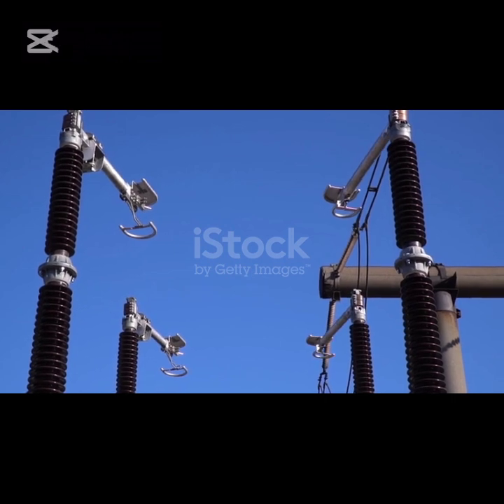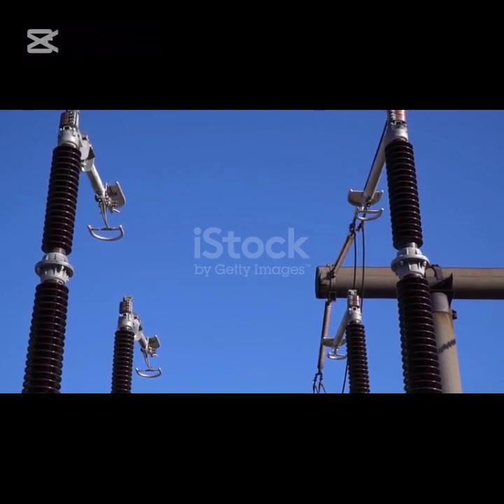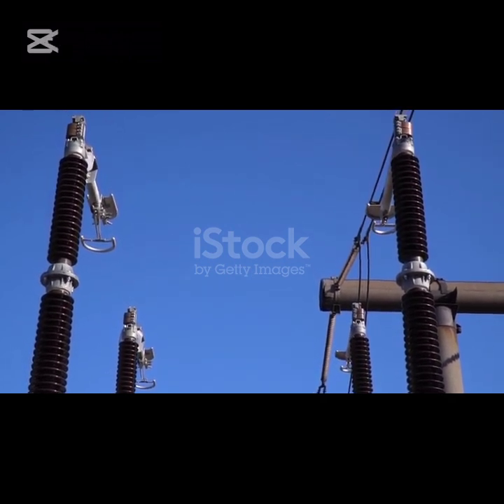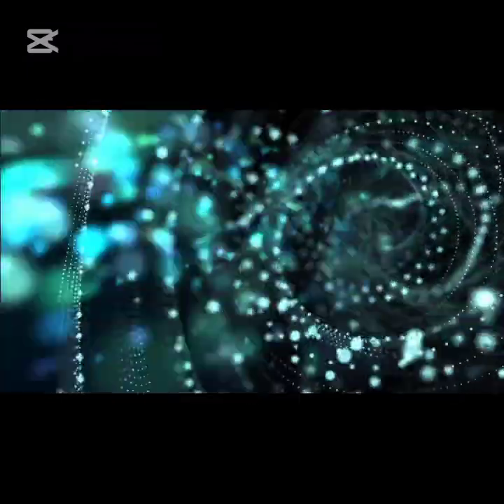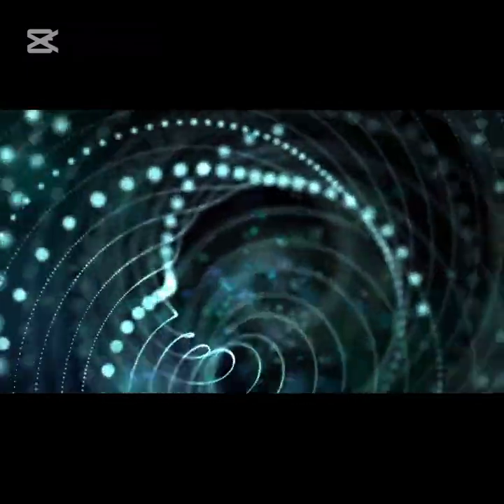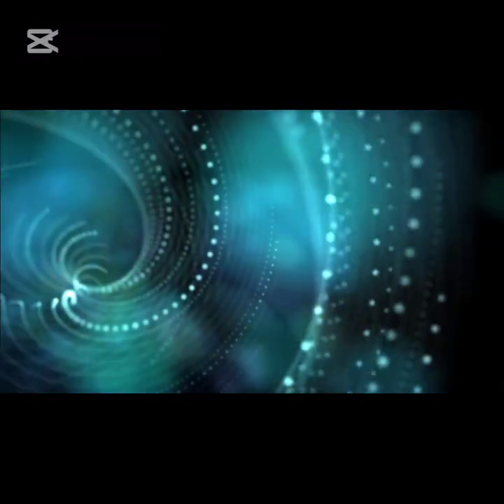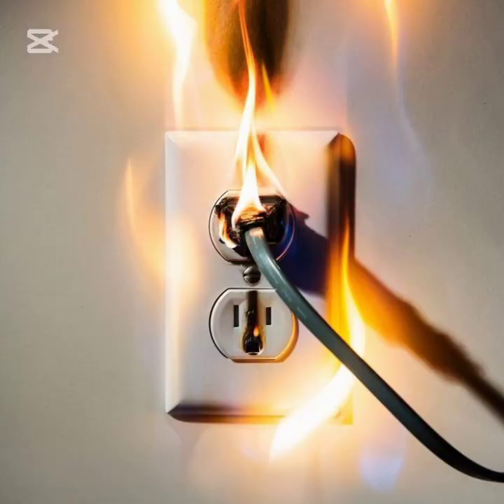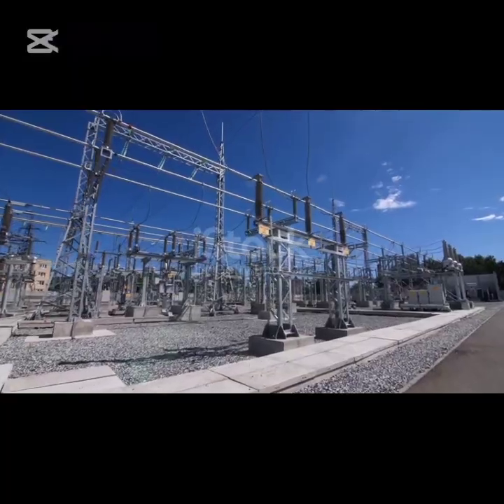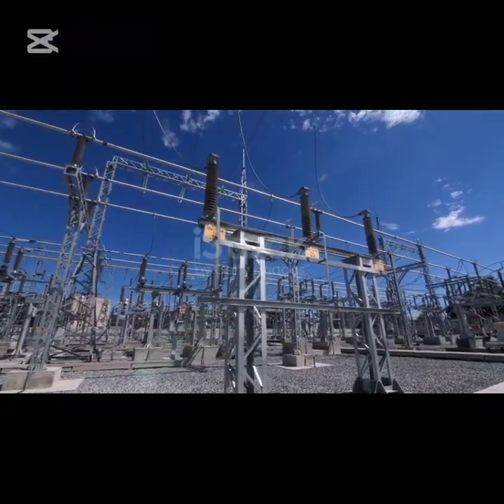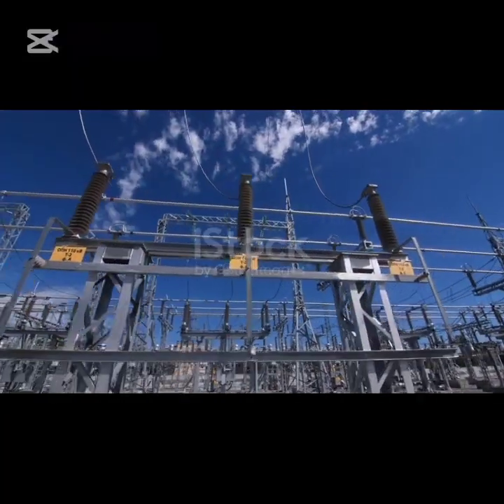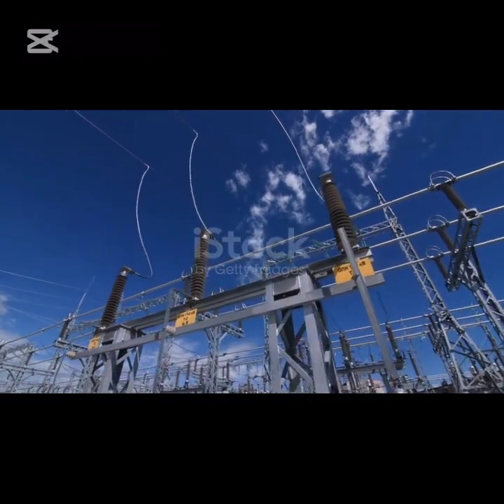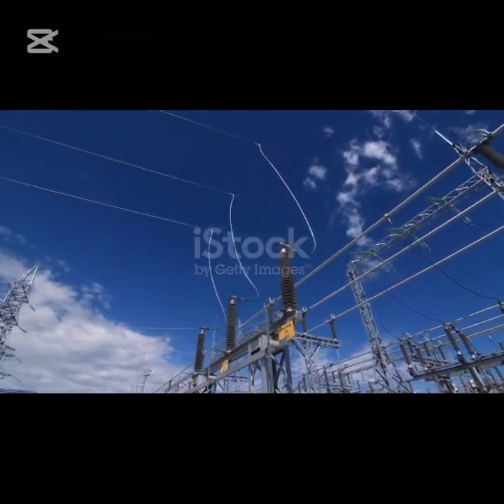Generally, as we have seen all the drawbacks of short circuit faults, it reminds us of the importance of designing and operating power systems with adequate protection and fault clearing capabilities to minimize the impact of short circuits. Let us now explore different methods to prevent or reduce their impact. Here are several effective methods to mitigate short circuits in power systems. 1. Proper system design. Use well-designed electrical layouts to minimize fault risk. Ensure equipment is rated correctly for expected loads and conditions.